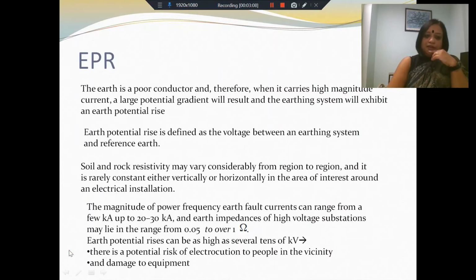In this respect, we define what is called EPR, or the earth potential rise. Now, the earth is a poor conductor. It has high values of resistance. Ordinarily, the current through earth is very small, and therefore the IR drop, the potential drop between two points which are earthed, does not matter. It is insignificant.